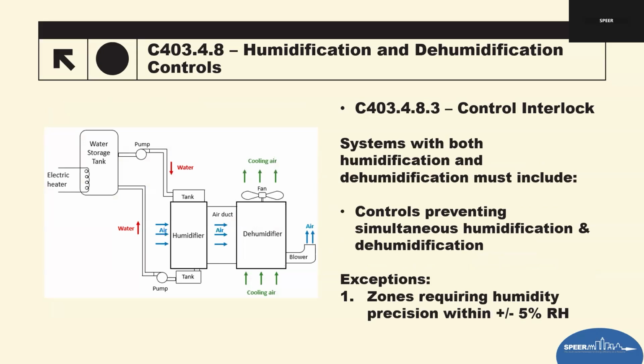And then sticking to that, we also now have a control interlock. This requirement basically ensures humidification and dehumidification equipment cannot run at the same time. Yeah, that probably does happen from time to time. It's not commissioned properly or someone's put the settings in incorrectly. Systems must have a control interlock, either mechanical or DDC based. This prevents one system from adding while the other one's trying to remove it.